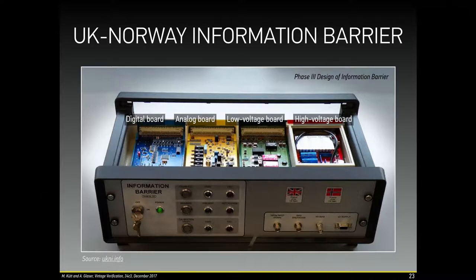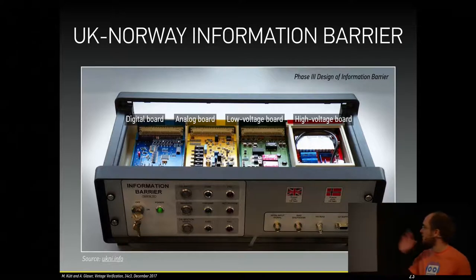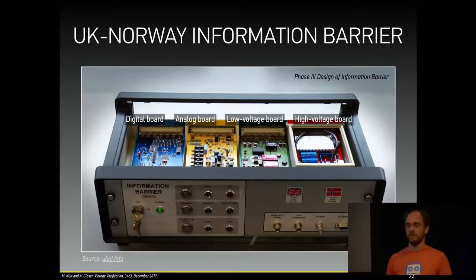They wanted a simple device, as simple as possible, using off-the-shelf hardware, and they wanted it to be modular. So you see it's divided not only by geometry but also by color, into a digital board, an analog board, a low voltage board, and a high voltage board. They also wanted it to operate from battery, so it's independent of a power supply, and they wanted it to be very robust for use and very clear while using it. So they came up with these three buttons, with green LEDs in the middle circles and red LEDs around them.